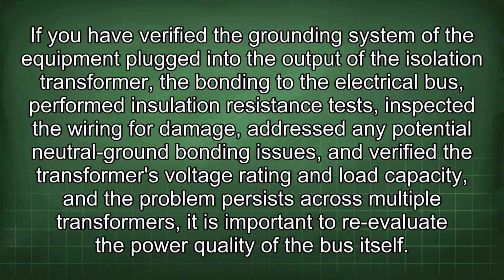If you have verified the grounding system of the equipment plugged into the output of the isolation transformer, the bonding to the electrical bus, performed insulation resistance tests, inspected the wiring for damage, addressed any potential neutral ground bonding issues, and verified the transformer's voltage rating and load capacity, and the problem persists across multiple transformers, it is important to re-evaluate the power quality of the bus itself.